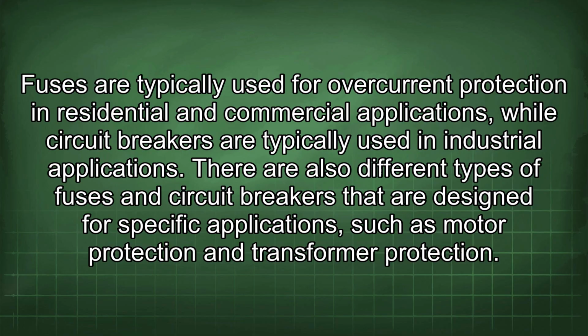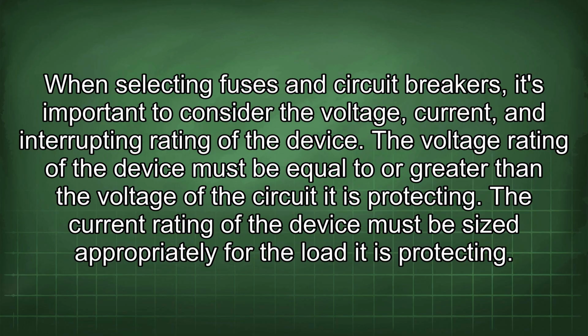Fuses are typically used for overcurrent protection in residential and commercial applications, while circuit breakers are typically used in industrial applications. There are also different types of fuses and circuit breakers that are designed for specific applications, such as motor protection and transformer protection. When selecting fuses and circuit breakers, it's important to consider the voltage, current, and interrupting rating of the device.